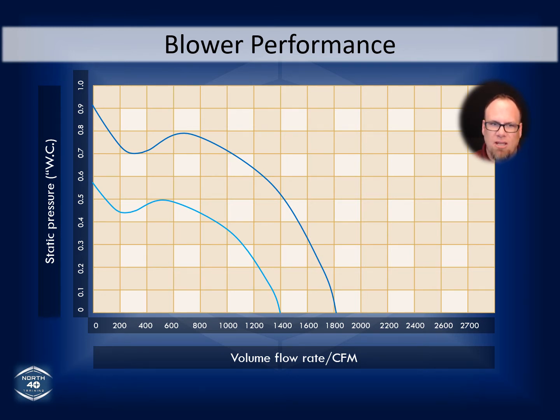On the left-hand side of this chart that you're looking at, you see numbers going up and down, and that's what's called static pressure. It's measured in inches of water column on a manometer. Now, static pressure is a fancy word for resistance. How much resistance is in that ductwork, and that's what you're measuring with your manometer. So going up and down that chart, as you go all the way up to the top and you see the number 1, that is 1 inch of static. In most applications, that is way more than you would ever want. Okay, but in this particular example, that's the maximum amount. You can't get any more than that.